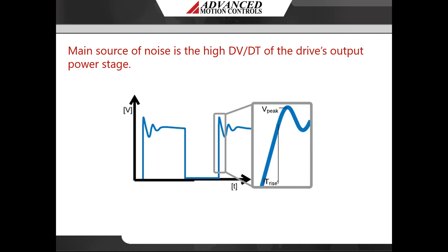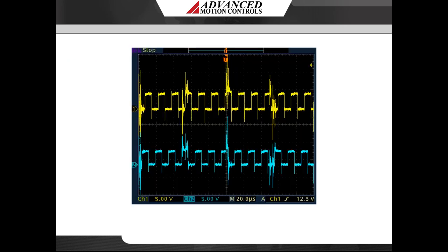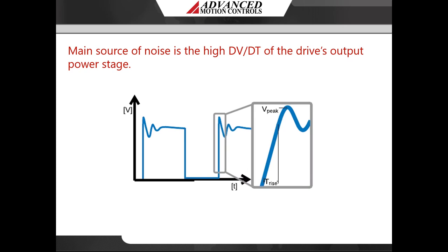The primary source of noise originates from the drive's output power stage, having a typical DV/DT of about 1V per nanosecond. The DV/DT refers to the change in voltage over the change in time. The active power devices modulate the full DC bus voltage by switching the transistors on and off very rapidly. The disadvantage to switching is that it generates electrical noise that disrupts other parts of the system. The output stage can transition from 0V to the full power supply voltage in nanoseconds. The high DV/DT that accompanies this PWM output can couple noise back to the signal lines.